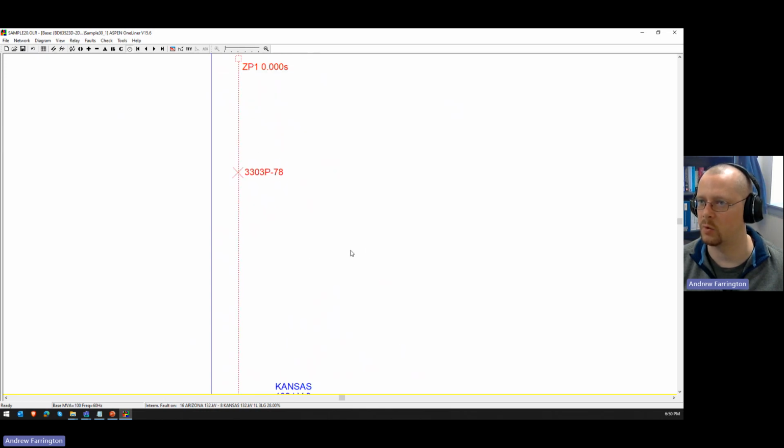So you can watch and say, okay, at what point does the zone 1 stop operating? Still operating, still operating, still operating. Oh, there it goes. Now it's operating on zone 2 in 1.5 seconds.